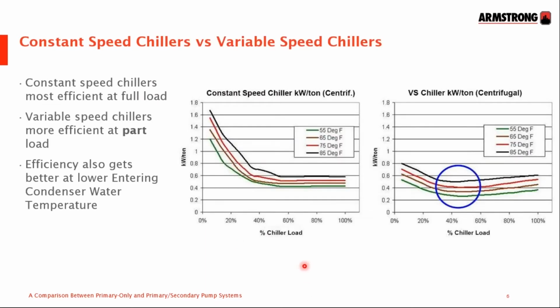The other piece to know about is that constant speed chillers have a different efficiency curve than variable speed chillers. By curve, I mean the relationship between loading of the chiller and its efficiency. You can see here that a constant speed chiller is most efficient, with the lowest amount of kilowatts needed for every ton of cooling provided, at full load. As you unload the chiller, the efficiency goes down. It requires more kilowatts for every ton of cooling.